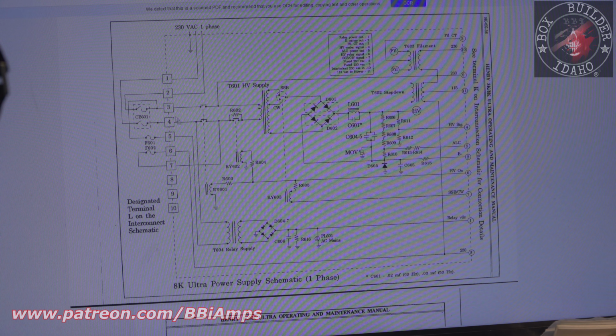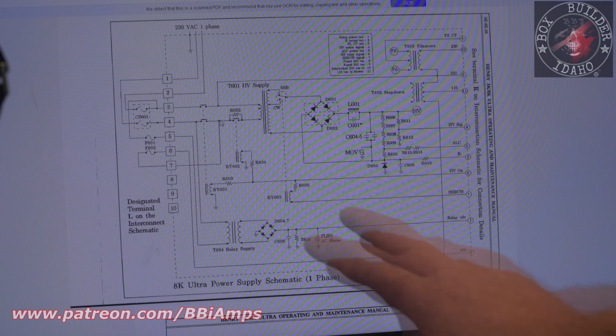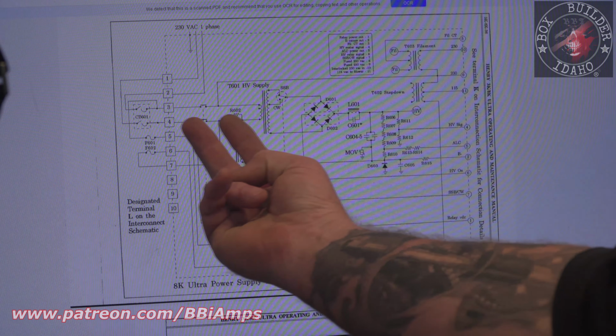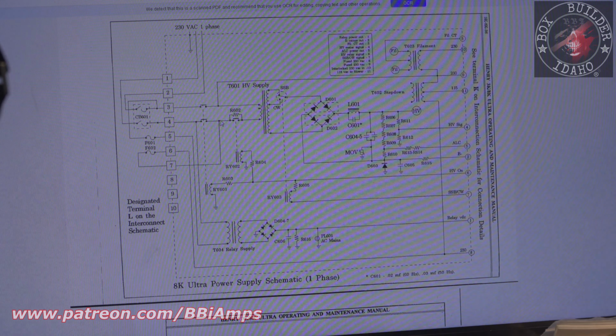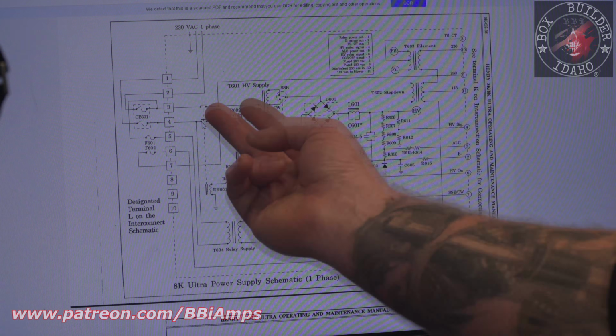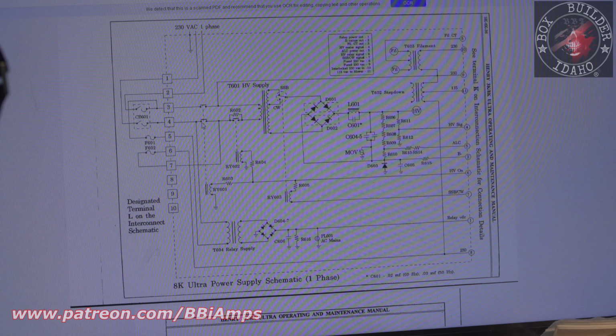This is wired all wrong. He has this wire here and this wire here, and that's why it won't turn on. He's got these two wires reversed. So when he put it back together after he blew up this contactor, I'd almost bet this contactor or this contactor, when he switched them out, he flip-flopped these two wires.